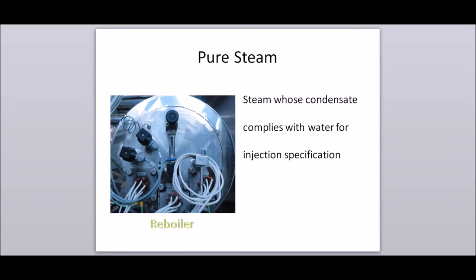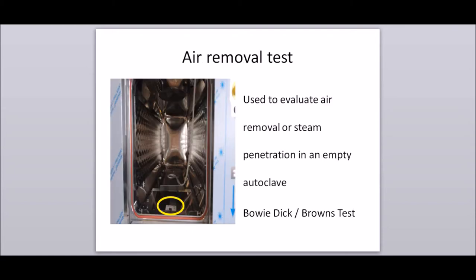Pure steam: steam whose condensate complies with water for injection specification. Pure steam is generated by a reboiler or pure steam generator, which has purified water or water for injection as feed.